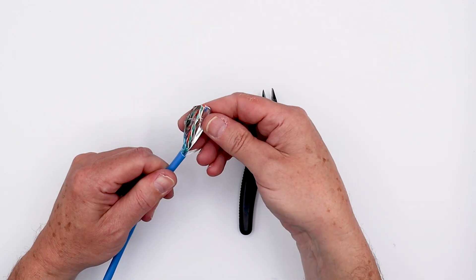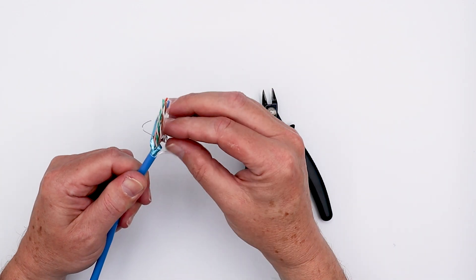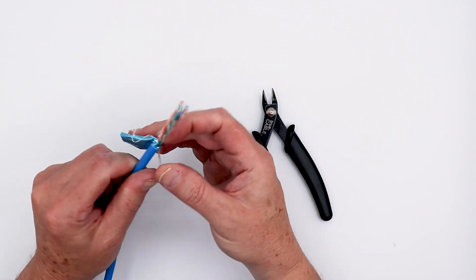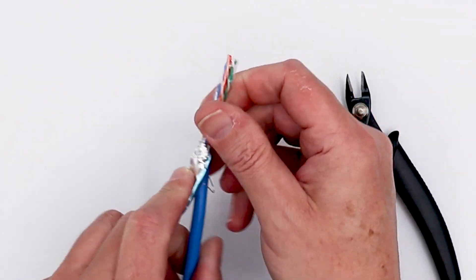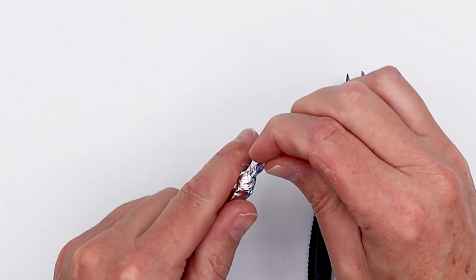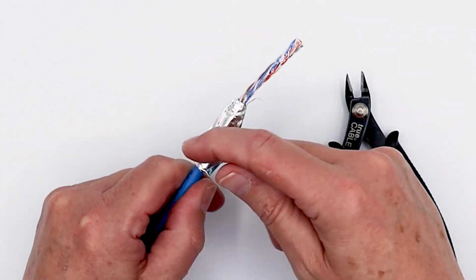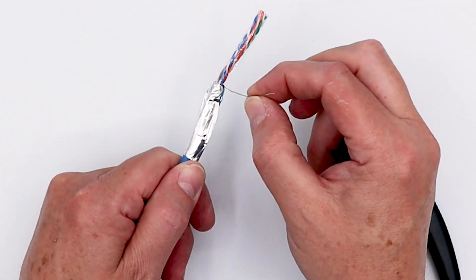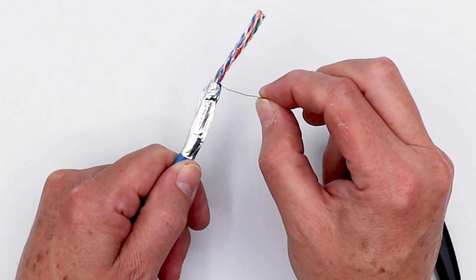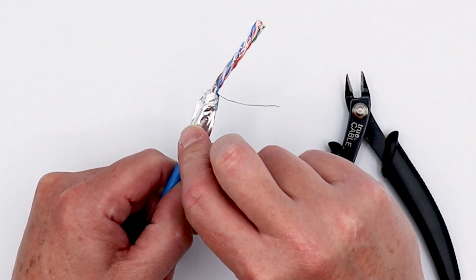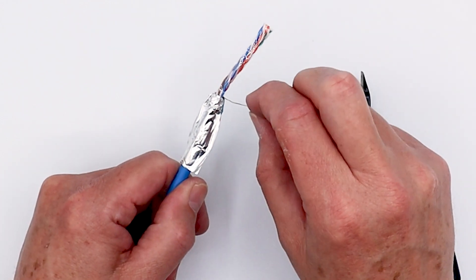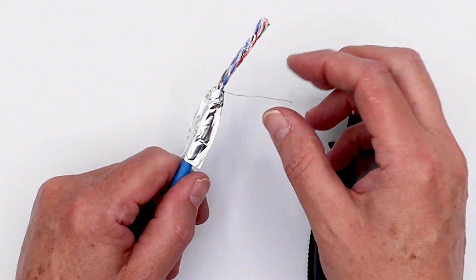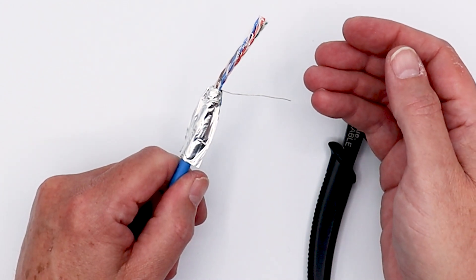Once you peel back this foil shield, you're going to notice that there's also a tinned copper drain wire, and this drain wire makes contact with the inside of the cable shield all the way along its length. This serves primarily as the ESD drain ground, and then the shield is bonded with this wire. Bonded means it's making a low impedance electrical contact.